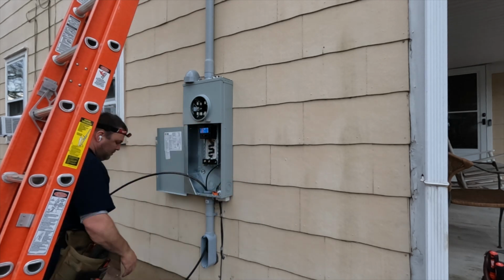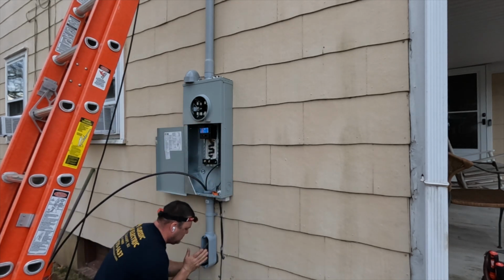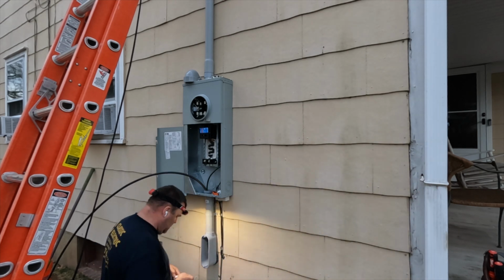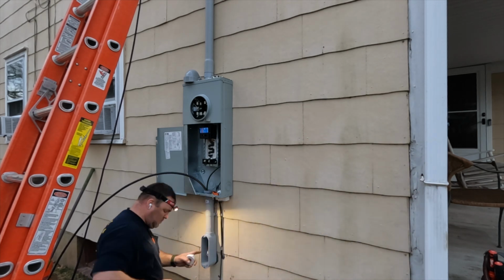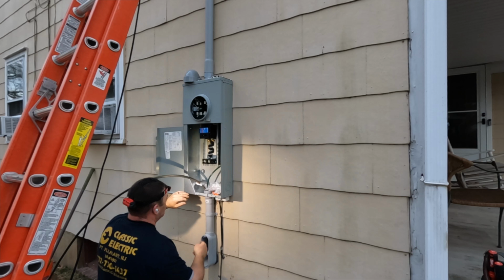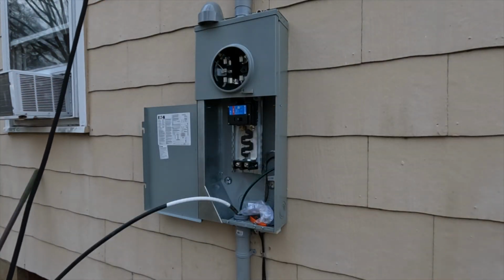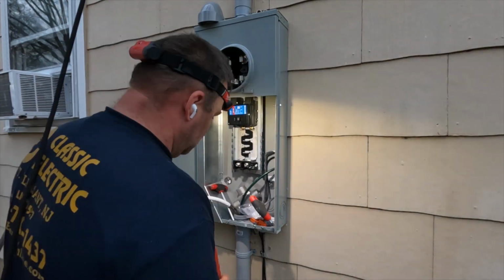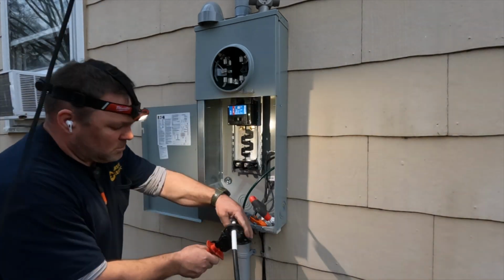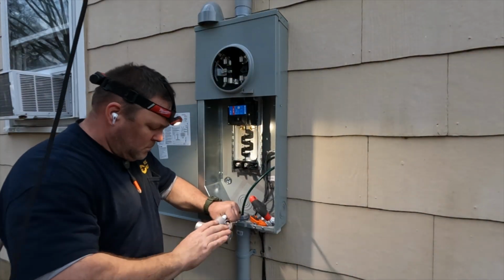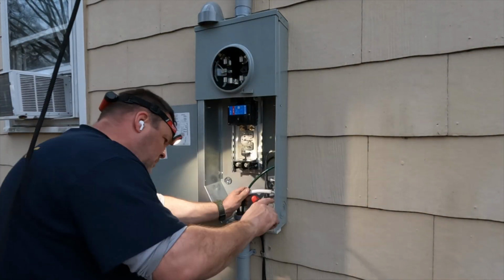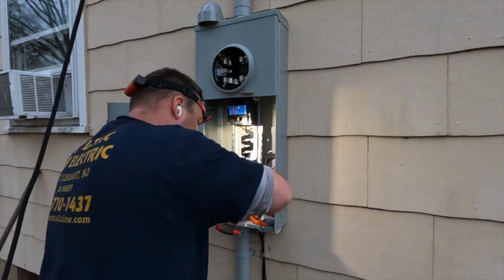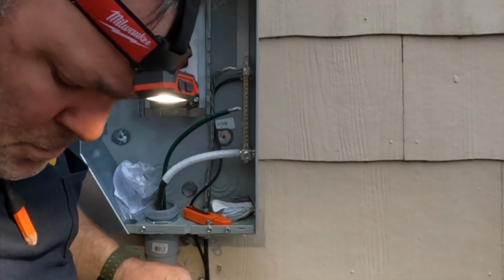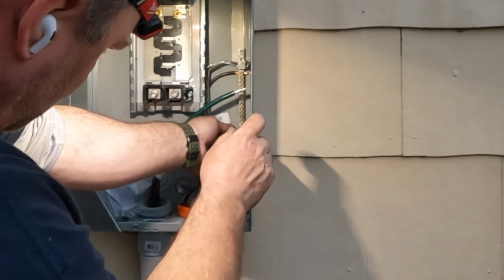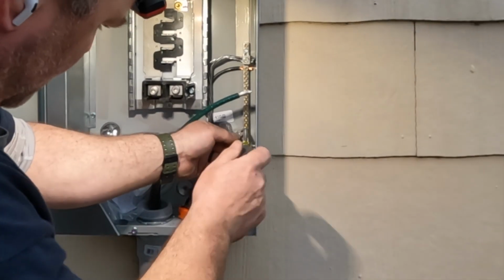other than cut in at the end of the day, is I'm installing my 4/0 aluminum service entrance conductors between the main breaker here and the panel downstairs, which are actually not service entrance conductors, they are feeders. It's a 4-wire. So we have two 120 volt legs, we have a neutral between them, and then of course our equipment grounding conductor, which gets derived here at the main disconnect. That equipment grounding conductor is the green cable that's been re-identified.